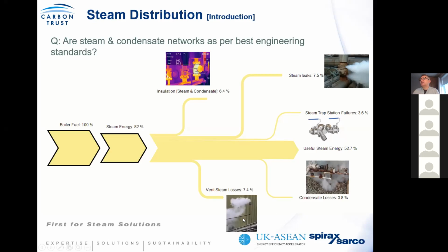Then you have your vent steam losses. And if you see here a vent from a condensate recovery unit, you have a lot of flash steam losses. What you should be doing is conducting a steam trap survey using Spirax Sarco's expertise, because we know exactly where and why the losses are occurring. And if unavoidable, we can then say what can be done. But a good indicator you have a problem with the distribution system is if you see a lot of flash steam potentially coming from a condensate recovery unit. So in other words, address the source of the problem.